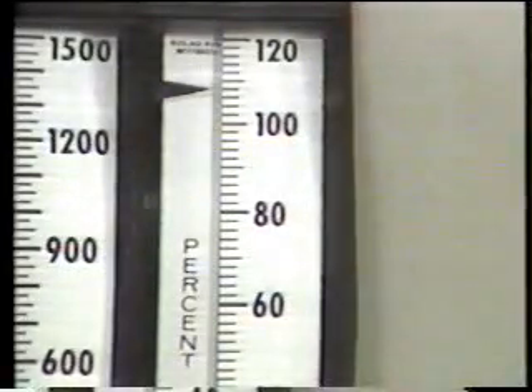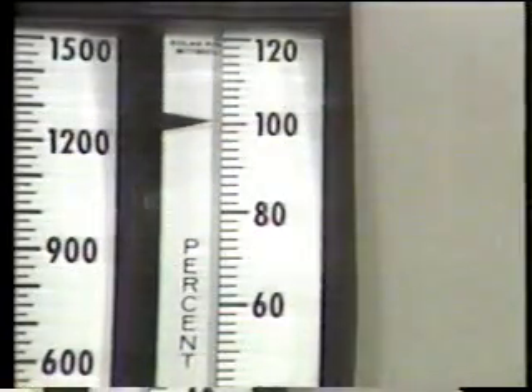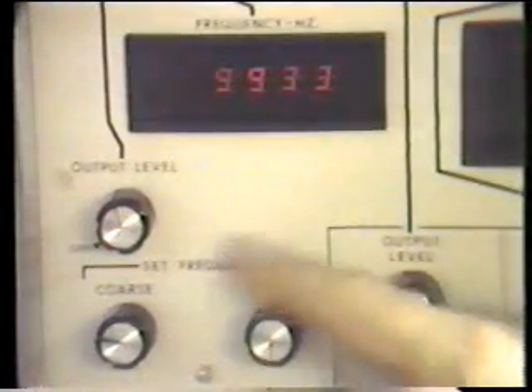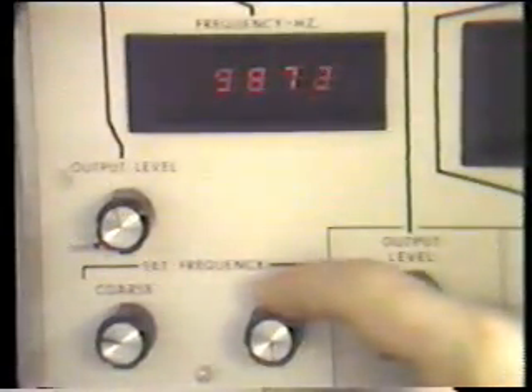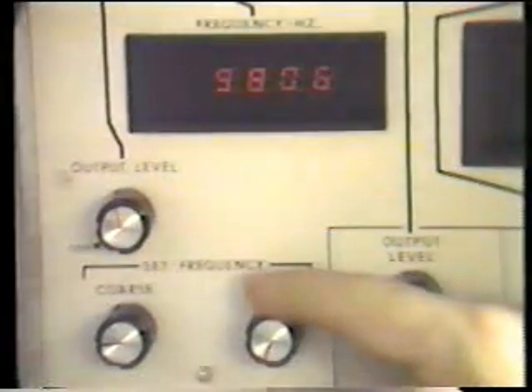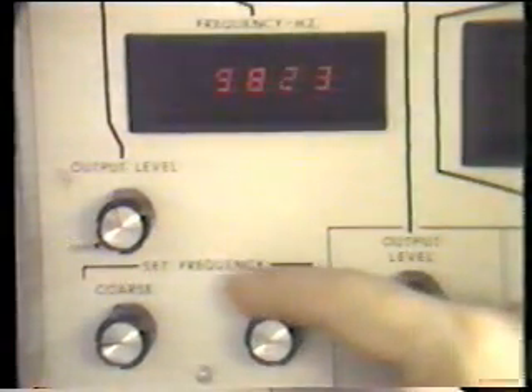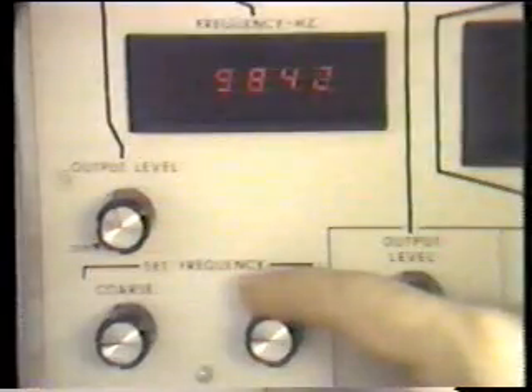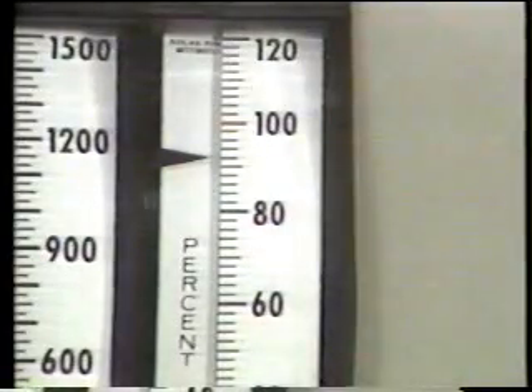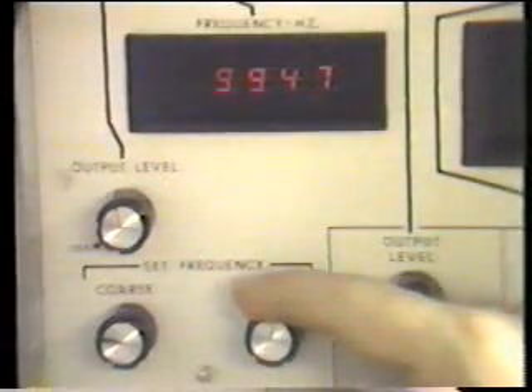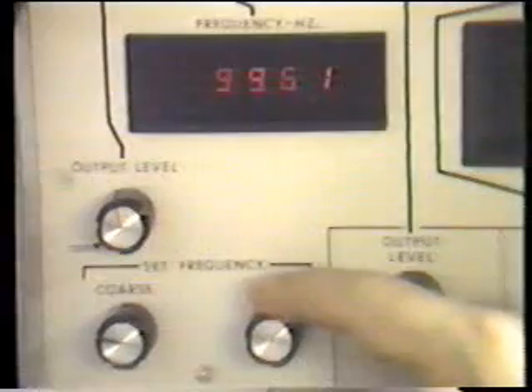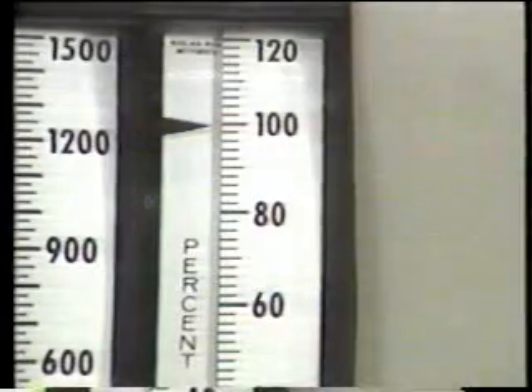Now you're ready to recheck the speed control unit set point at 100% speed by approaching the frequency from below 100%. Begin by lowering the signal generator frequency below 100% speed. Observe the digital counter and speed meter for a frequency drop. Check that the speed meter indicates less than 100% speed. Now, slowly increase the signal generator frequency. The speed meter should indicate 100% speed at the correct input frequency.